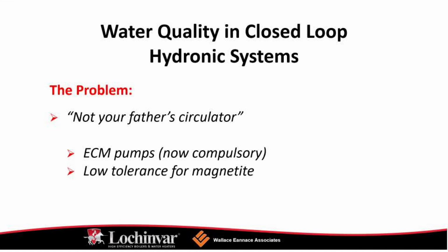So we want to be able to compete against water quality when facing this in closed loop hydronic systems. So something to always make yourself aware of. Again, bad water is going to equal premature component wear, breakdowns, downtime, callbacks. It's also going to greatly reduce heat transfer rates, up to 15%, and it will affect your efficiency rates too.